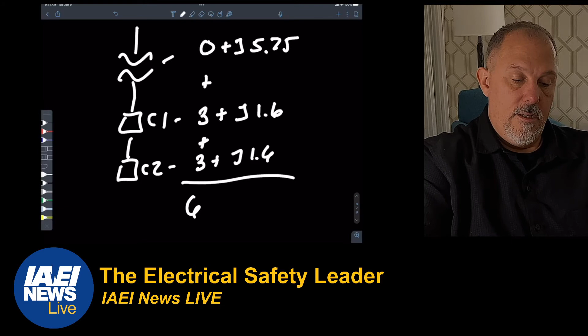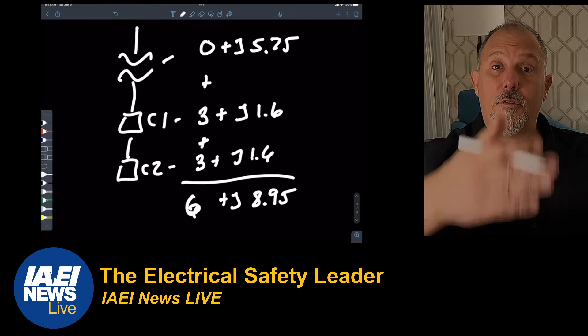5.75 plus 1.6 plus 1.6 is J8.95. And that's the total impedance for those components in series. That's the power of it, and then how would I use that is to calculate fault current. If that's the impedance, V is equal to IR, and I know the voltage, V over the impedance is current. That's the fundamentals of a fault current calculation right here.